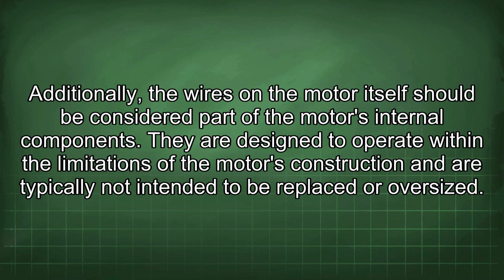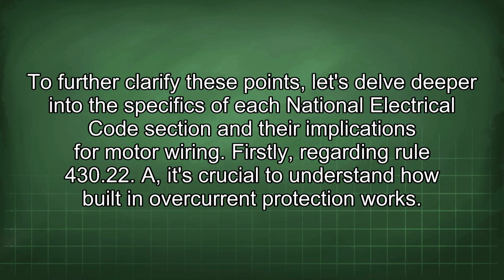They are designed to operate within the limitations of the motor's construction and are typically not intended to be replaced or oversized. To further clarify these points, let's delve deeper into the specifics of each National Electrical Code section and their implications for motor wiring. Firstly, regarding Rule 430.22 A, it's crucial to understand how built-in overcurrent protection works.